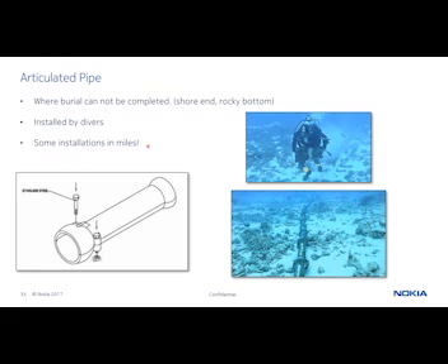So that first cable I showed you, from 1973, had about 10 miles of articulated pipe. It's like a suit of armor - this piece here is like a cuff on your wrist, about that size. You can see this guy showing them here; they clamp together and then you bolt them together. Here they are on the bottom of the ocean, with the guy literally walking on the bottom installing these. It's good revenue for divers in not-too-deep water where we can't bury the cable, and sometimes these are bolted to the ocean floor too if it's really rocky. We call this articulated pipe or split pipe. There are newer designs now that click and lock instead of using bolts, saving a lot of labor. Can you imagine doing this for 10 miles? But it's done.